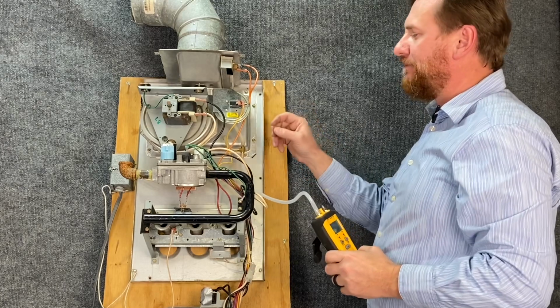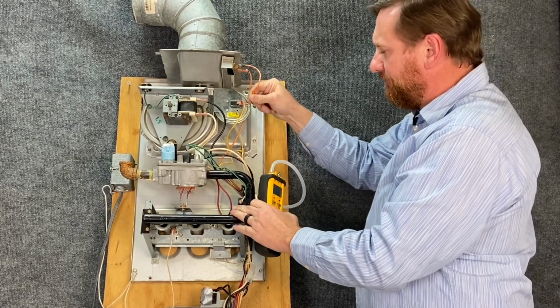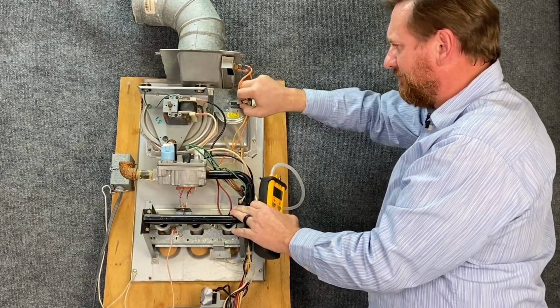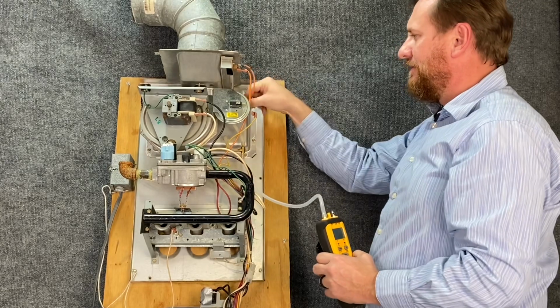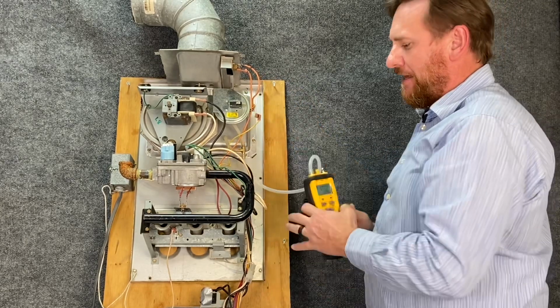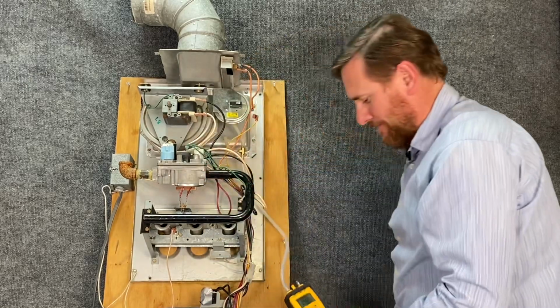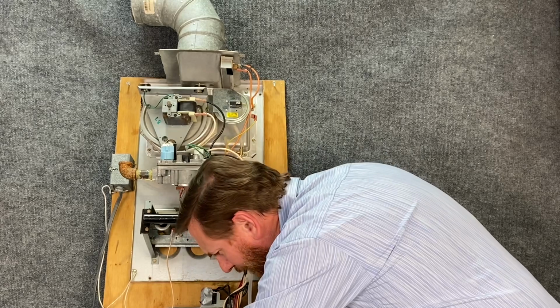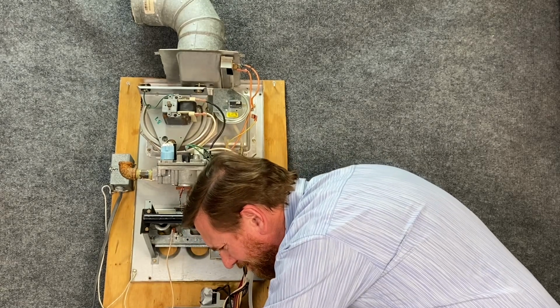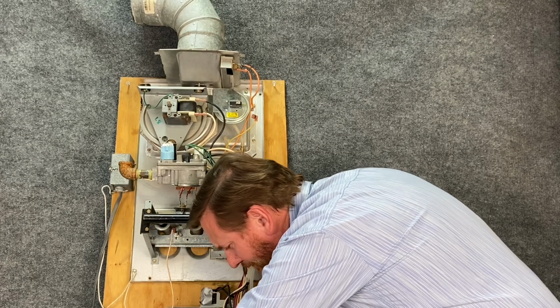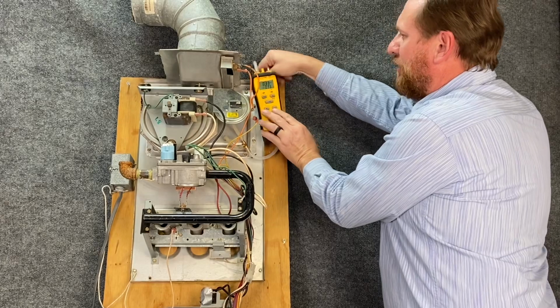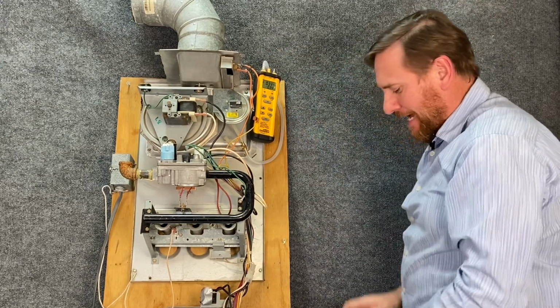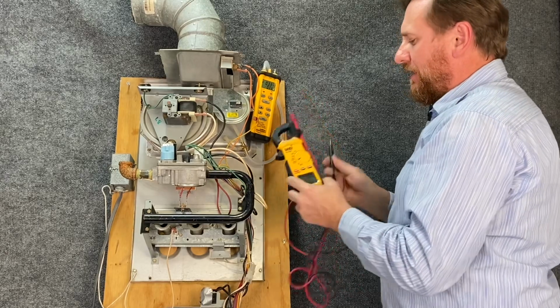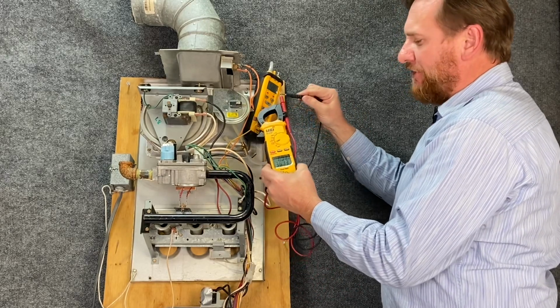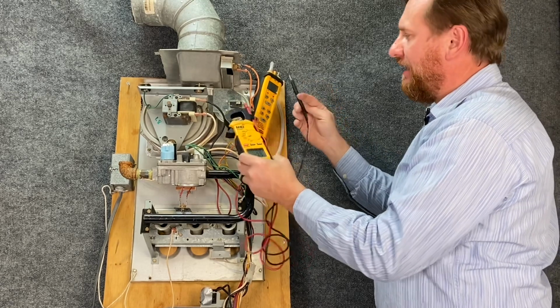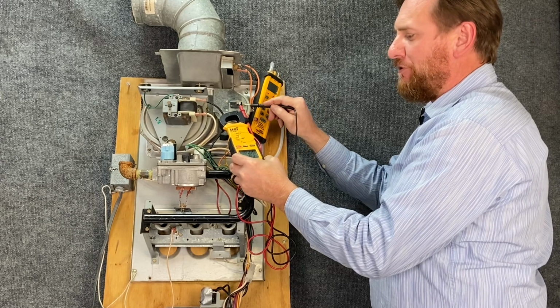There is, however, another way to check it. What we can do is pull these wires loose, and I can have a call for heat. And with my manometer, I know I'm pulling the proper vacuum. I can then take my meter and turn it to ohms. OL, infinite resistance, open. And if I touch the terminals together, I get zero resistance, closed. If I check across the switch, I'm showing 0 ohms of resistance.